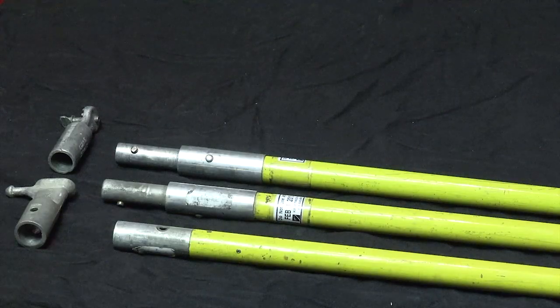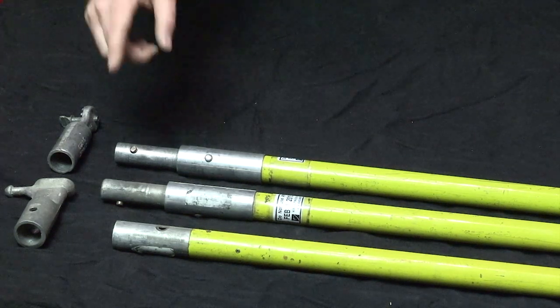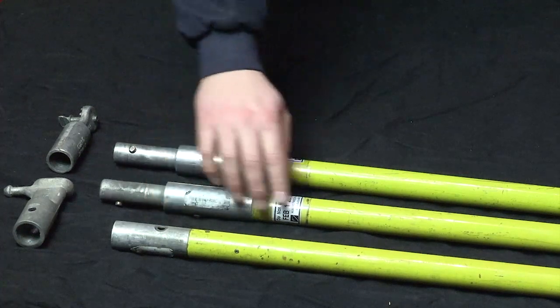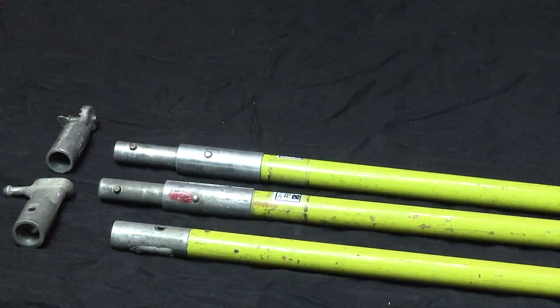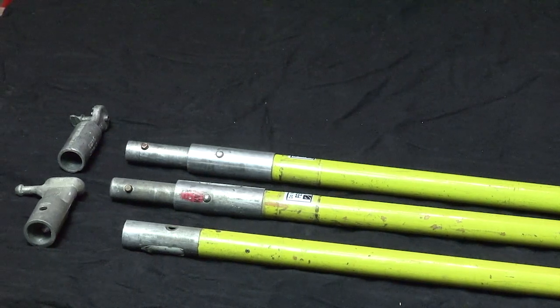Ensure that the stick you select is the proper length to allow for the required limits of approach. Do not encroach on these limits by choking too far up on the stick. Remember that the top metal portion of the stick is not considered insulated, so measurements must begin after this point.